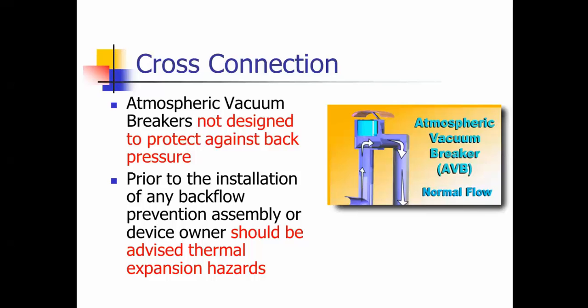Prior to the installation of any backflow prevention assembly or device, the owner should be advised of the thermal expansion hazards. If you install any type of backflow device or assembly on a home where it turns it into a closed system, such as a dual check on a meter, you could create a problem with their water heater, so they need to put a thermal expansion tank on those.